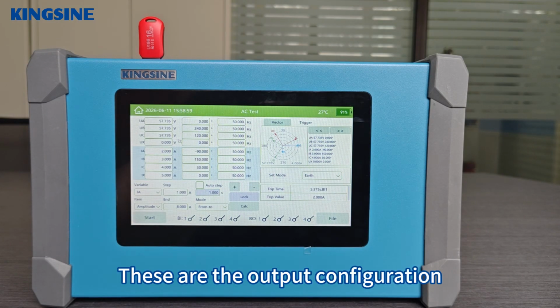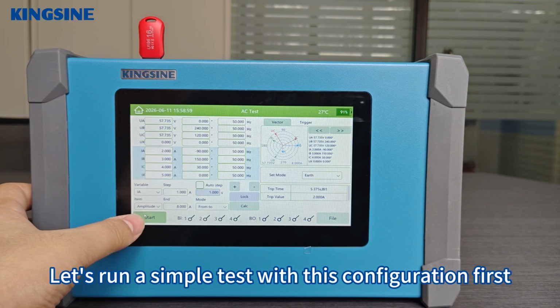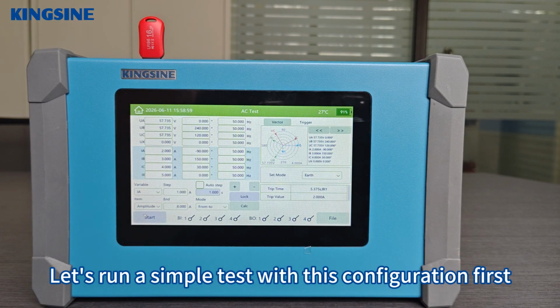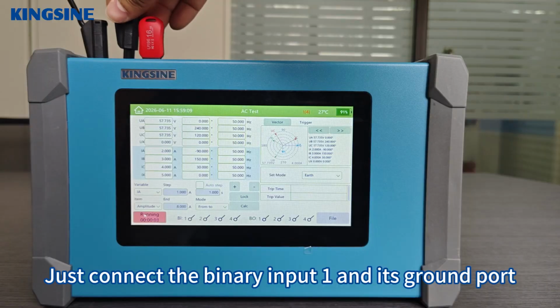These are the output configuration. Let's run a simple test with this configuration first. Just connect the binary input 1 and its ground port. So the trip time is 3.742 seconds and the trip value is 2 amperes.